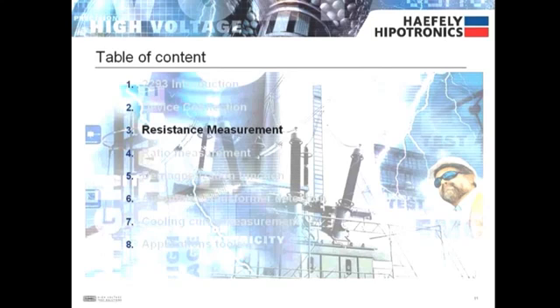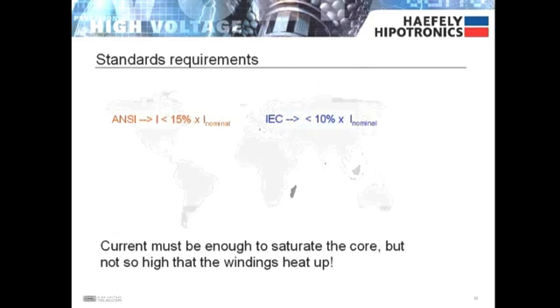Next is the resistance measurement mode. When performing a winding resistance measurement, it's important to use enough current to saturate the transformer core to obtain stable readings, but not so high that the windings heat up and provide faulty readings. The ANSI standards state that the current used should be less than 15 percent of the transformers nominal current, while the IEC states less than 10 percent.